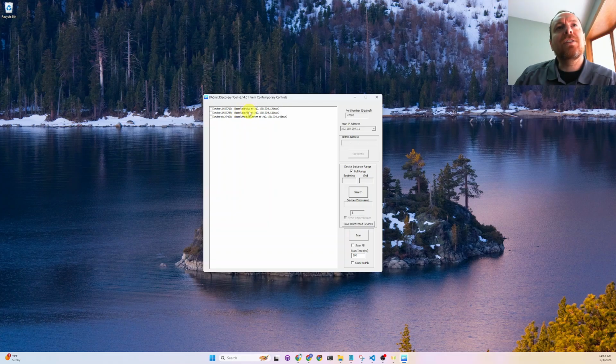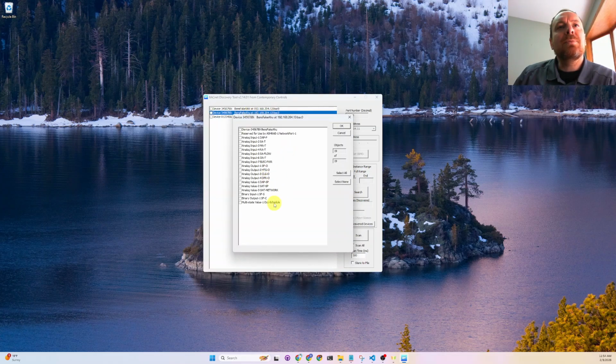I have a fake VAV box, a fake air handling unit, and also a fake building automation server that has a BACnet schedule point. This is just fake data, mimicking what an air handling unit would look like in the real world, with the supply fan speed command, heating output, cooling, damper, duct static pressure set point, supply temperature reset, a writable network outside air temperature point.